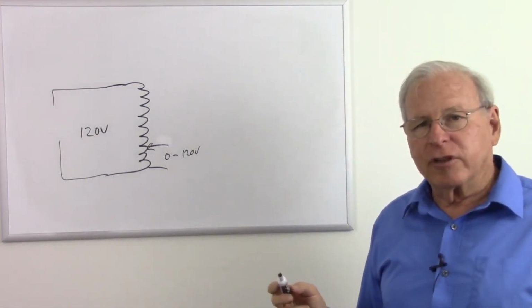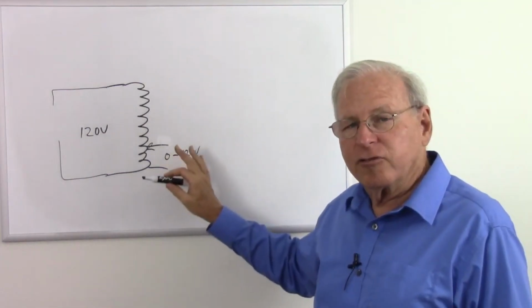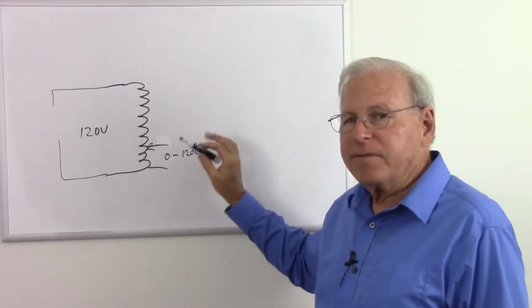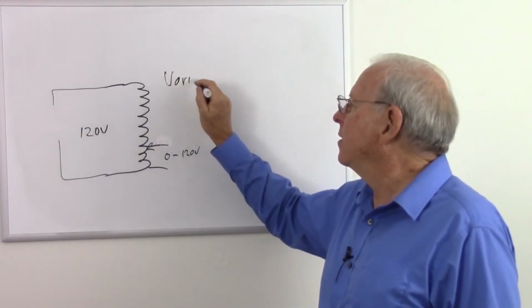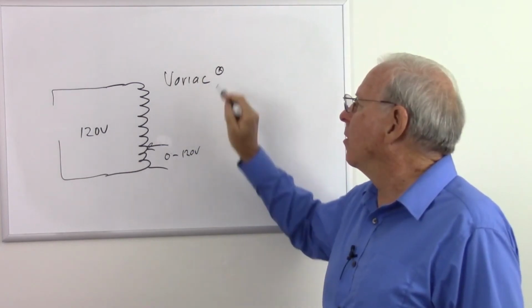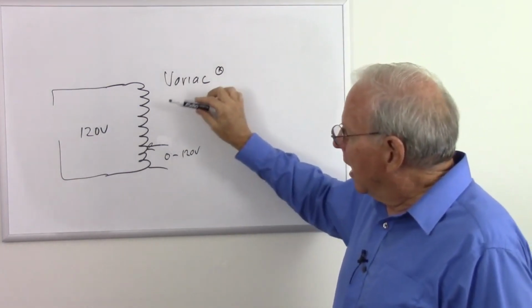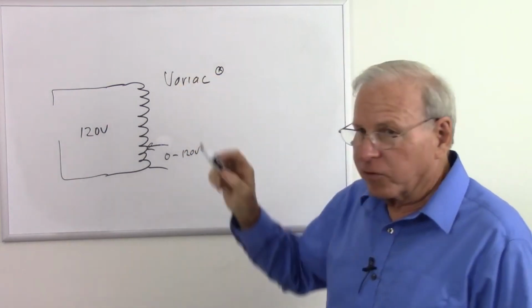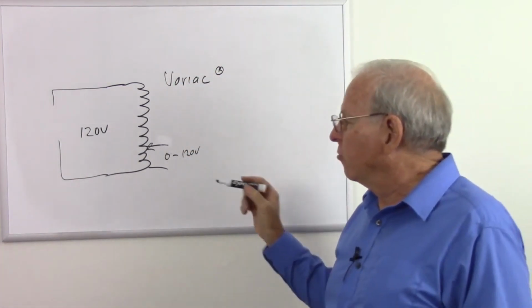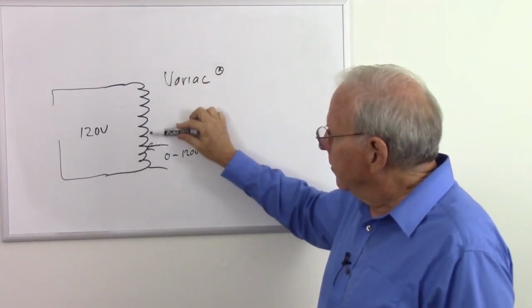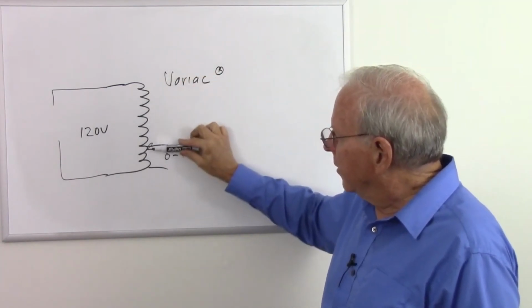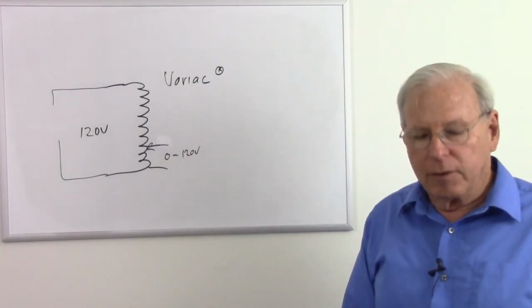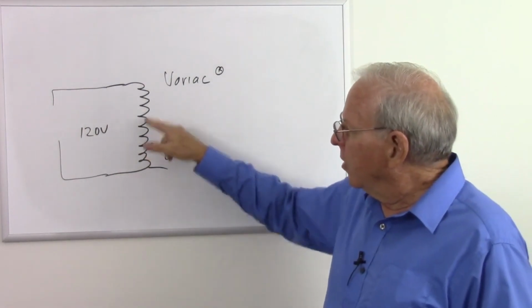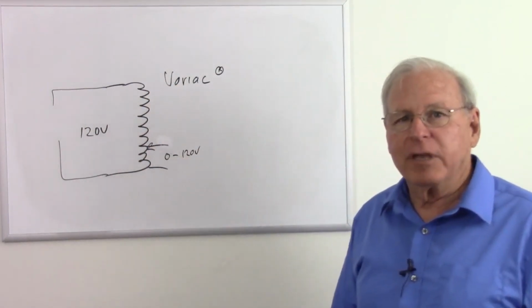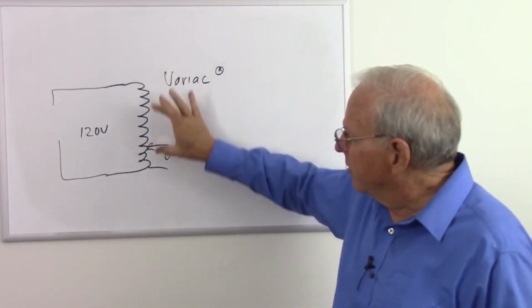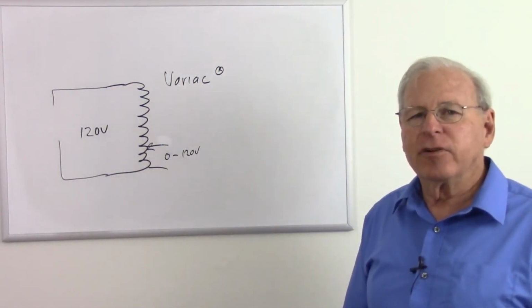Don't confuse that with an isolation transformer - they do have variable isolation transformers, but the variac, which is a brand name, is not an isolation transformer. It's a variable output auto transformer, just one winding, with a slider along it to get the proper output. So one coil, but it acts like two, because we still get mutual induction from this half over to that half, and vice versa.